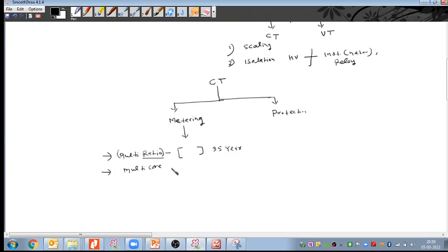And now when it comes to the multi-core CT, why do we use it? Because we have more than one function required in this current transformer.